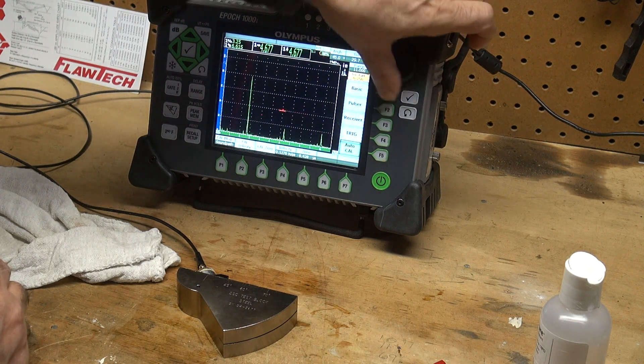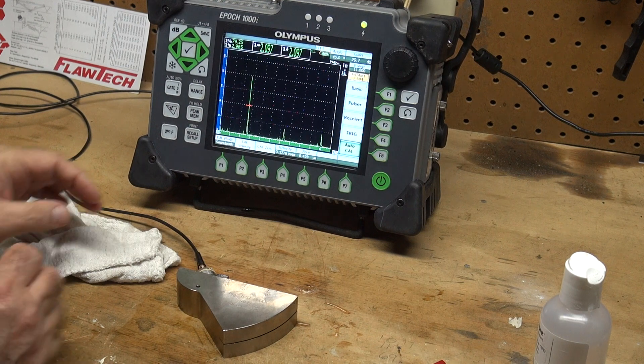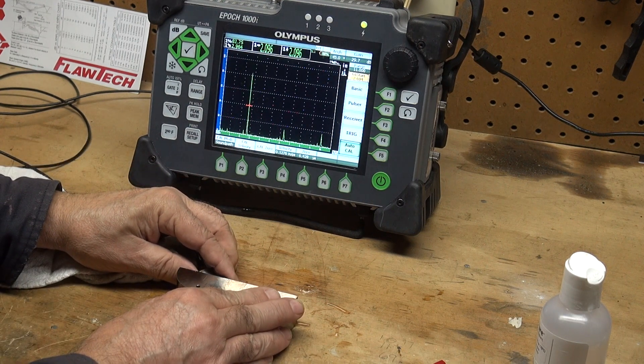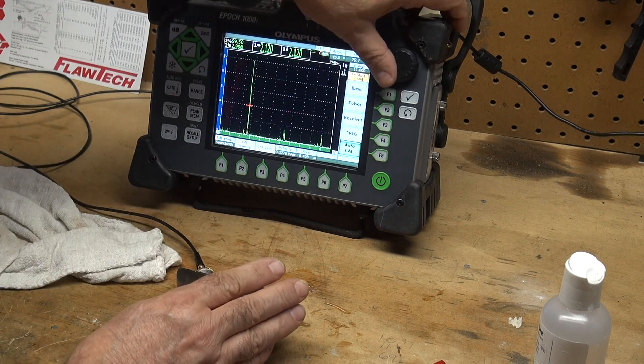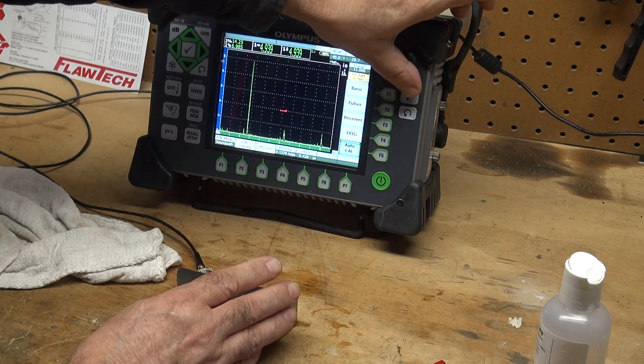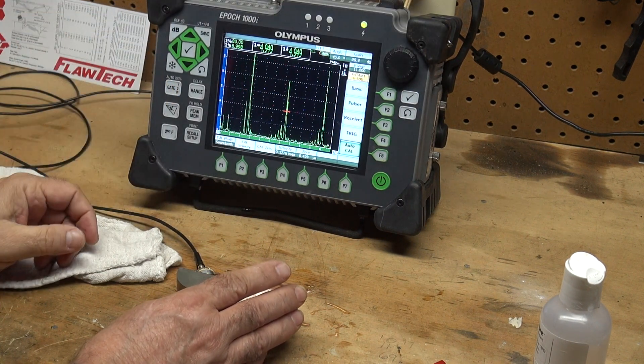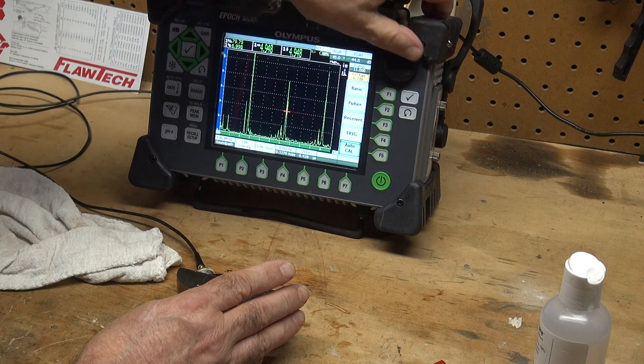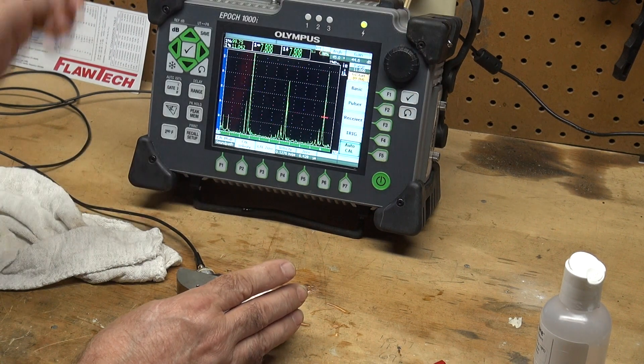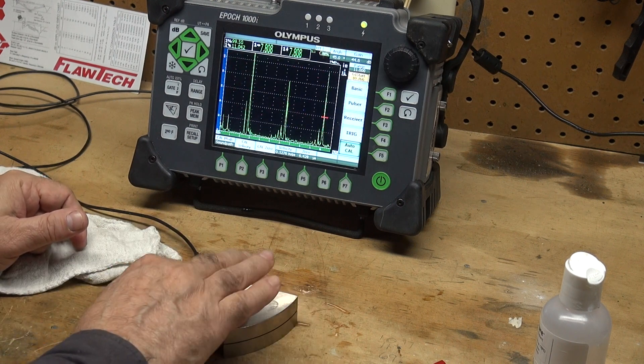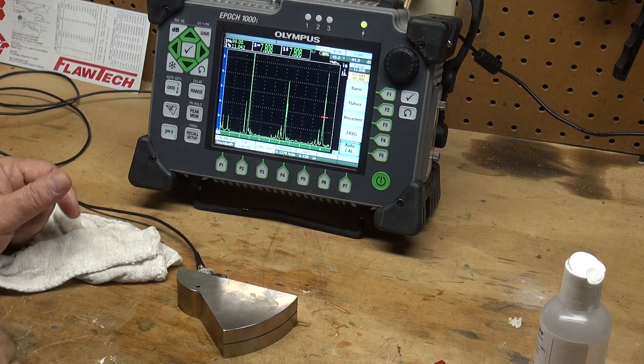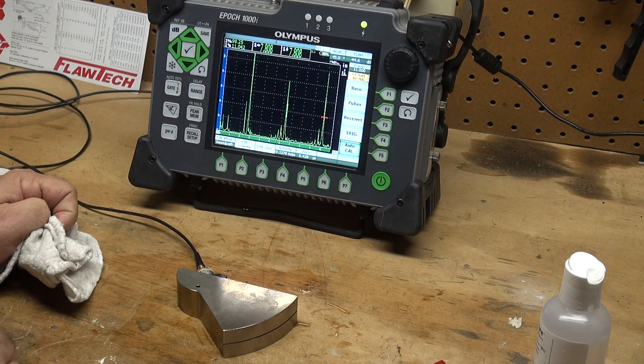So my gate, if I move my gate over here, capture this guy going in this direction, we have three inches. And then we will come over here and this radius will be seven inches. And then if you come all the way out here, this will be 11 inches sound path. So that's kind of some of the different reflected radiuses you get on this machine.